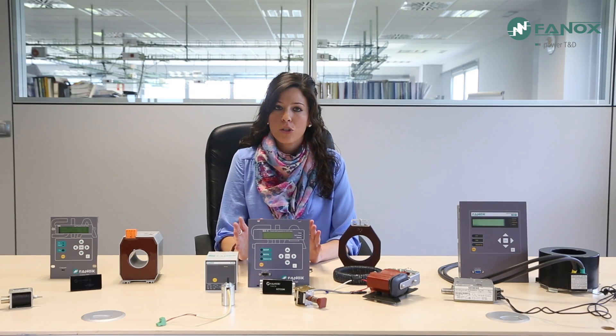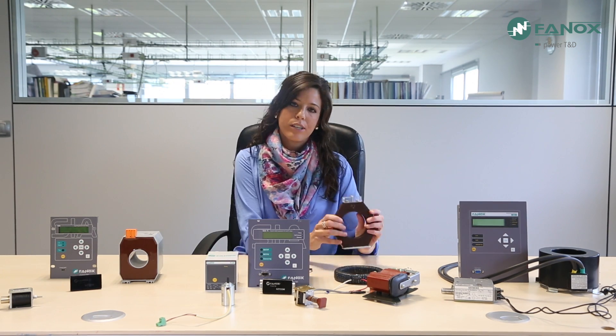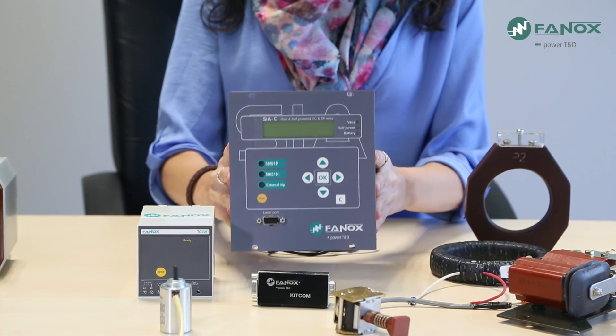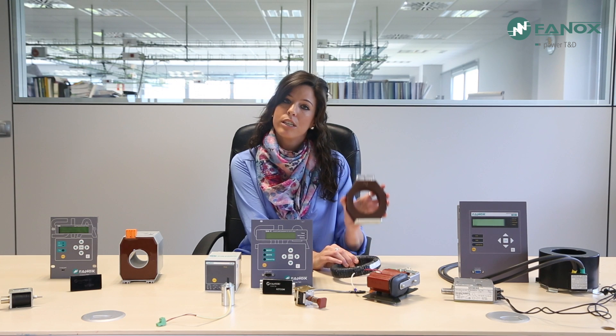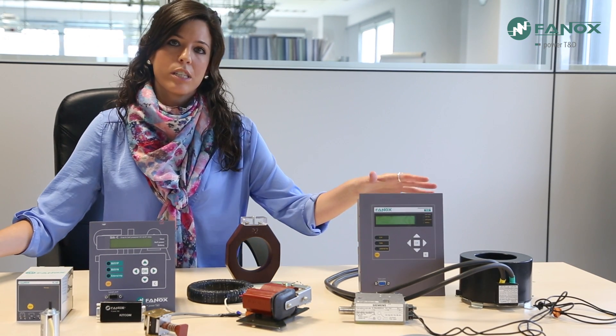Fanox offers a wide range of self-powered relays. The first classification is related to the transformers, depending on whether relays work with standard CTs or specific CTs. Standard transformers use a secondary equal to 1 Ampere or 5 Amperes. In this group, the SIAC relay stands out. Not only does it work with standard transformers, it also offers very low consumption. This allows the transformers to have a low burden — approximately 2.5 VA for a 1 Ampere secondary, and approximately 5 VA for a 5 Ampere secondary.